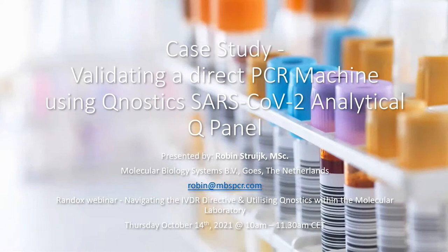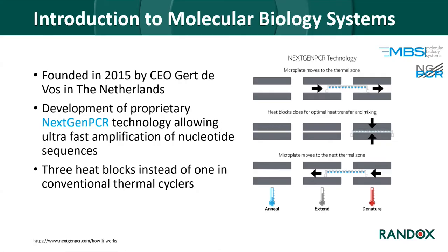Good morning everyone. My name is Robin Struijk. I've been working as a scientist in research and development for about four months at MBS in Goes, the Netherlands. I would like to thank the organizers at Randox for inviting us to present our exciting new PCR system. Molecular Biology Systems was founded back in 2015 by our CEO Gert de Vos in the Netherlands. The main core business is development of a new PCR cycler that, due to new technology, allows ultra-fast amplification of nucleotide sequences much faster than conventional PCR, possible because the machine contains three heat blocks instead of one.